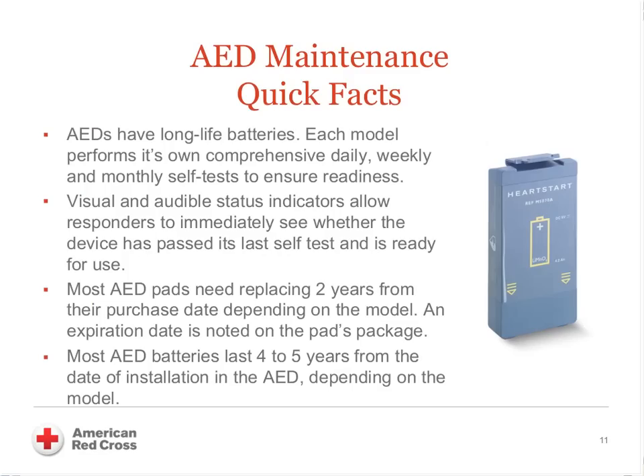Let's talk about the maintenance of AEDs. AEDs have a long battery life, and each model performs its own comprehensive daily, weekly, and monthly self-assessment to make sure it's ready for use. Some have visual or audio indicators — you might see a little X if it's not running properly, or a blinking green light if it is running properly. AED pads need replacing normally every two years, with the expiration date right on the package. Most AED batteries can last anywhere from four to five years, depending on the model.